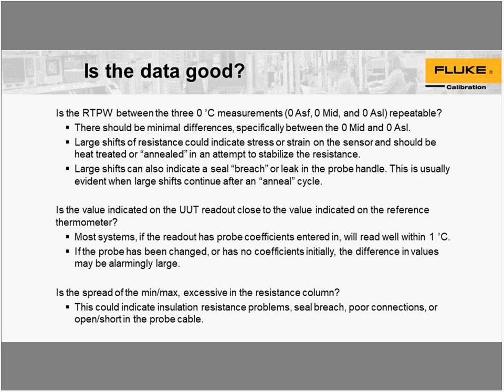Okay. Large shifts can also indicate a seal breach or a leak in the probe handle. That's usually evident when large shifts continue after an anneal cycle. Okay. Is the value on the UUT close to the value indicated on the reference thermometer? If the readout probe has had coefficients entered in, it will read well within 1 degree Celsius. Okay. Your error should be fairly small. If the probe has been changed for one that was bad before, or you don't have any coefficients in there, you could have some extraordinarily large numbers and they may scare you.